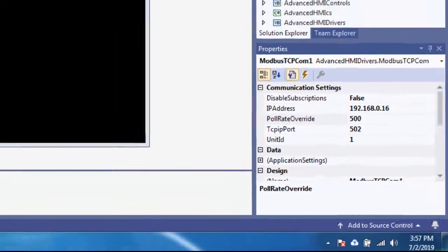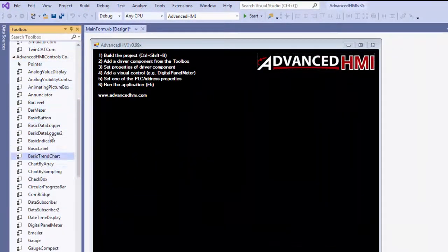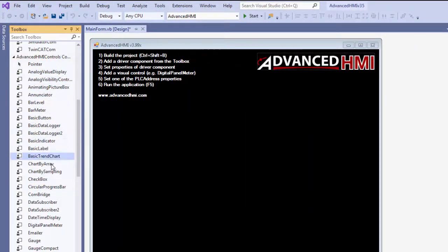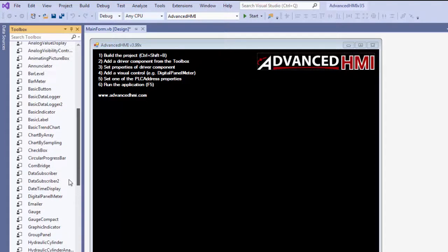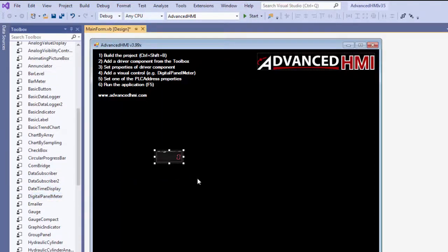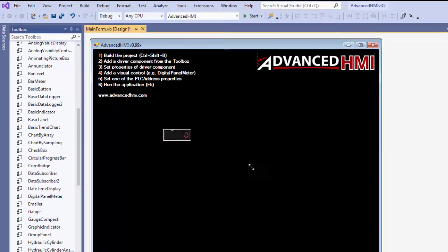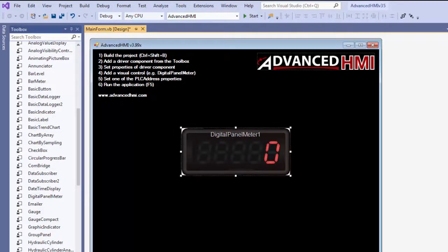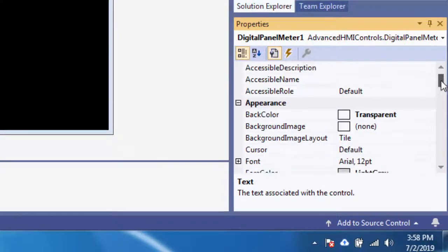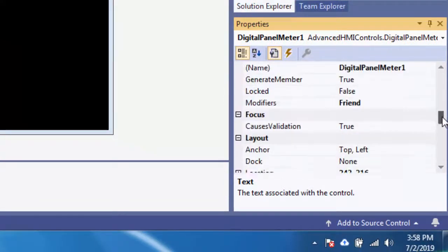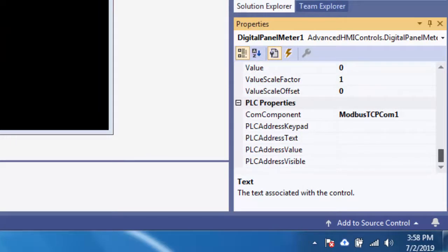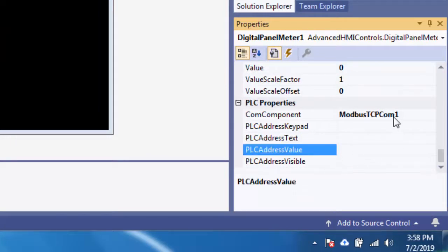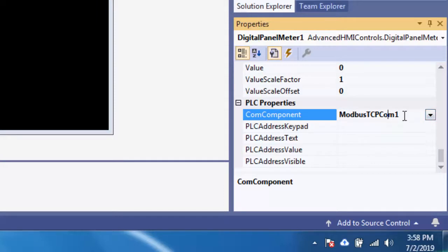And then I can go to any one, well, any one of these that can display an analog value. I have all sorts of things like displays and charts and gauges and all sorts of things there. I'm just going to take and drag and drop a digital panel meter and do like that. And then I'm going to specify a holding register. I'm going to go down there. PLC address value. It's using the com component Modbus TCP com. Right. So you're telling it to use this particular driver.